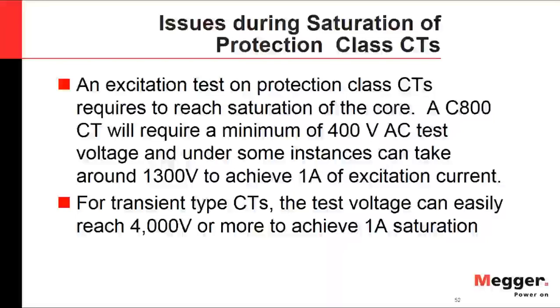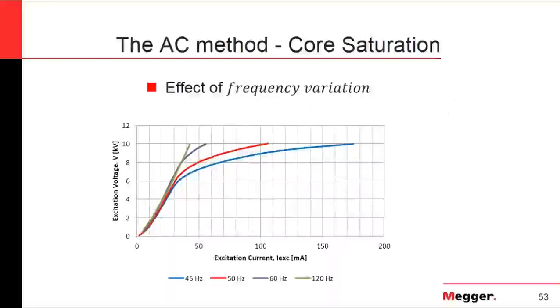If you are in the field with a typical instrument providing 2000 V AC output and 1 A, and that is not enough to reach saturation, you will not be able to obtain the saturation curve. One approach is to change the test frequency: as you lower the frequency, the voltage needed to reach saturation decreases. The saturation curve at 60 Hz requires more voltage than at 50 Hz, which in turn requires more than at 45 Hz.